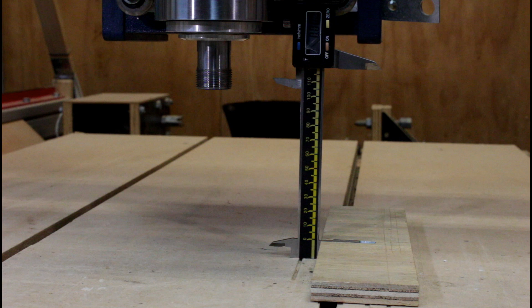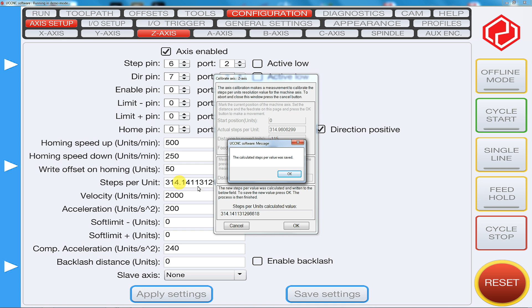Well, that's 115.3 millimeters. At the completion of the axis movement, it comes up with this distance measured unit box, which lights up, and we can enter in our measured distance. In this case, 115.3. Then I go OK, and it recalculates a new steps per unit, which I can accept by going OK, and it updates it over here, and just go OK here.